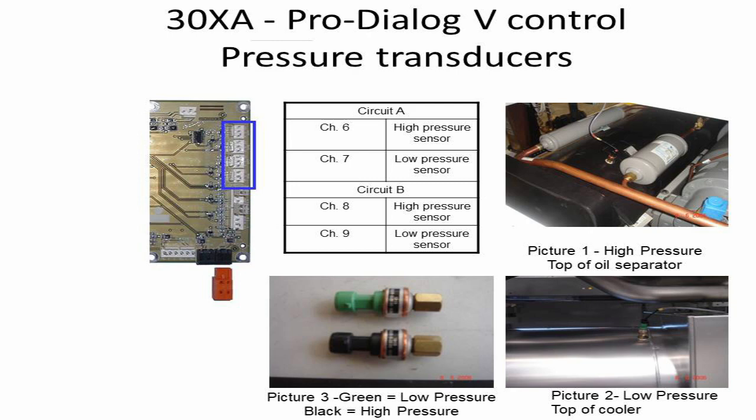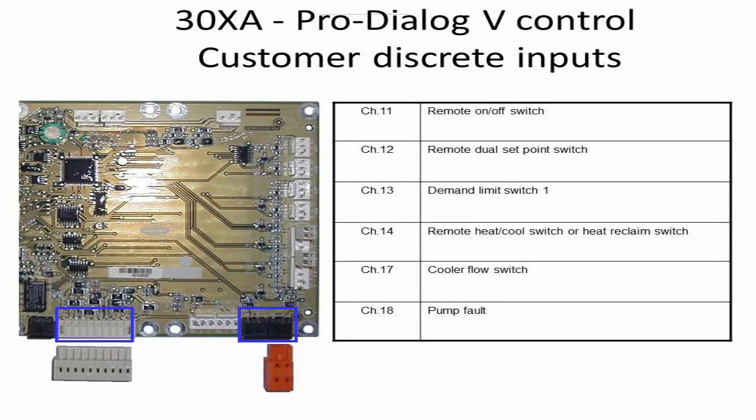The high pressure transducer and low pressure transducer for Circuit B are connected on Channels 8 and 9. Picture 1 shows the physical location of the HP transducer installed in the chiller. Picture 2 shows the physical location of the LP transducer installed in the chiller. Picture 3 shows the colors of the transducers. This slide shows the connection locations on the main baseboard along with a table of input signals and their names with respective connection channels on the baseboard.